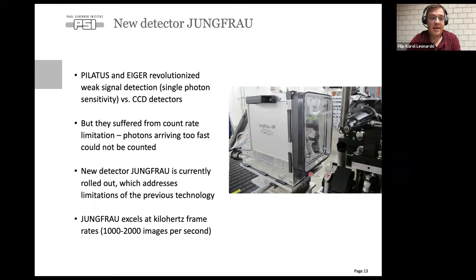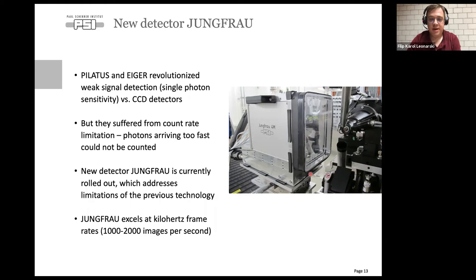We are currently rolling out a new design. While Pilatus and Eiger were extremely good at looking at weak signals — we could see a single x-ray photon very clearly — they suffered from counter overflow limitations which limited the dynamic range, especially at very fast frame rates. We have a new design called Jungfrau, also named after one of the highest Swiss mountains.